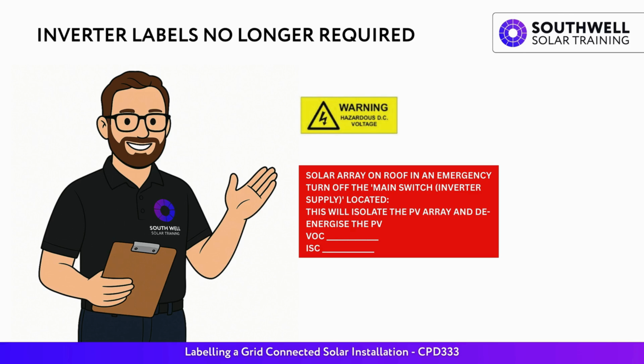Inverter labels no longer required. Number 1. Warning: hazardous DC voltage. This label was previously used for systems exceeding 600 volts DC. This is no longer required as the previous voltage requirements no longer apply, so do not install this label even on commercial systems. This label can be used for a very small amount of systems in very limited situations, so you may want to keep 1 or 2 of them, but we'll go through that later on in the course.